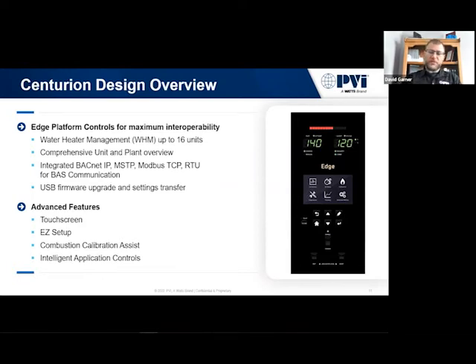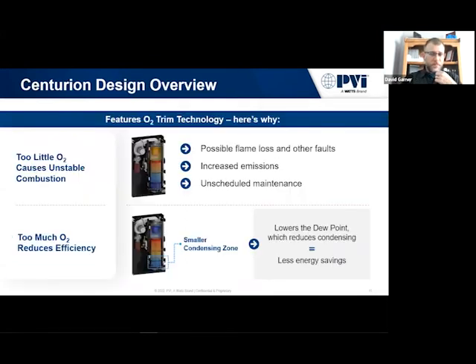So if we can make sure there's flow on the system, the unit's going to come on, it's going to go 100% fire rate. It's going to go through and actually trim itself, set its combustion where it needs to go, and then go down to 80%, trim itself, and so on, and so on. So it will do its own temporary startup just to get us through a little tight period where we need to be able to have domestic hot water.